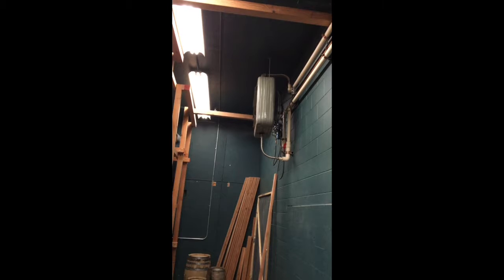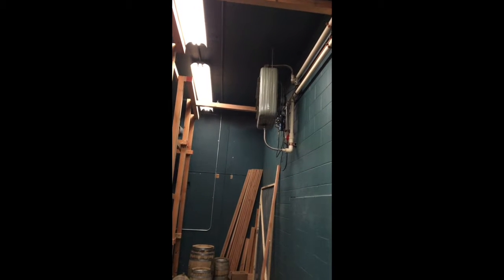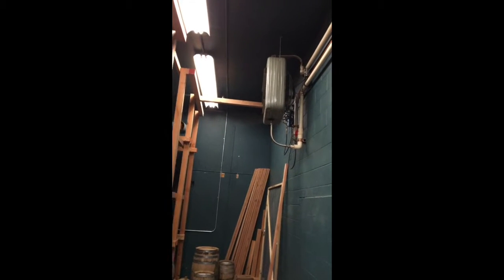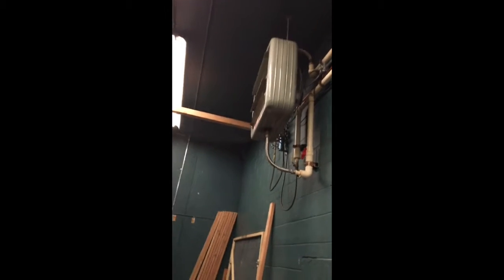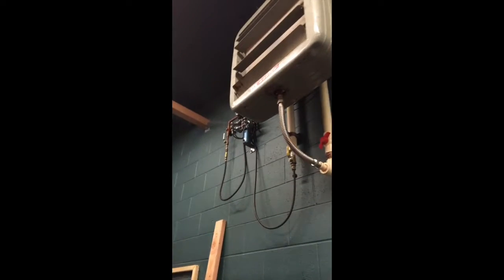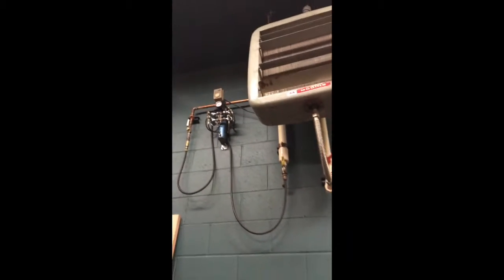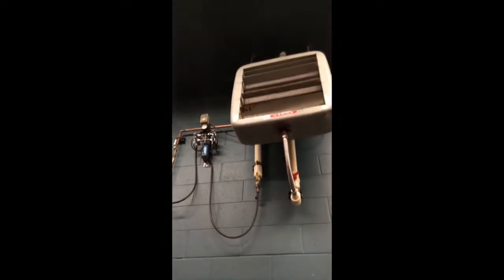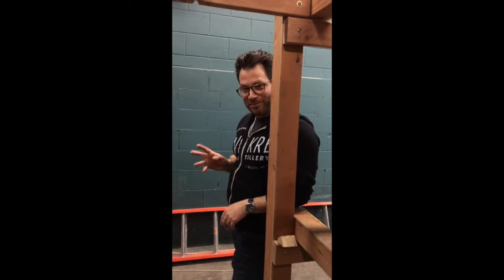So that hot water coming off the still house and the brewery, we run it over here, and we have these fan coil units. That hot water runs through radiators, a fan blows the heat out, and behind it we're also humidifying using some of that warm water, so that this barrel room is as obnoxiously loud, obnoxiously hot, and obnoxiously humid as possible.